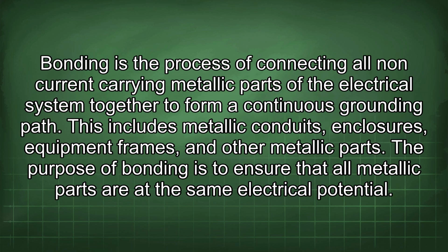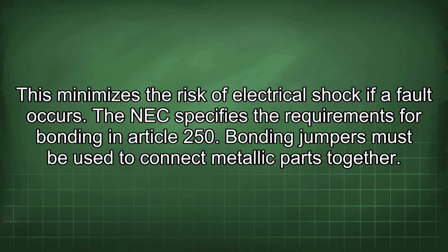Bonding is the process of connecting all non-current carrying metallic parts of the electrical system together to form a continuous grounding path. This includes metallic conduits, enclosures, equipment frames, and other metallic parts. The purpose of bonding is to ensure that all metallic parts are at the same electrical potential. This minimizes the risk of electrical shock if a fault occurs. The NEC specifies the requirements for bonding in Article 250.